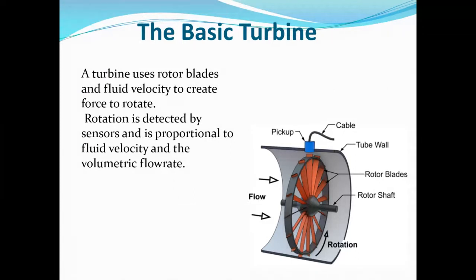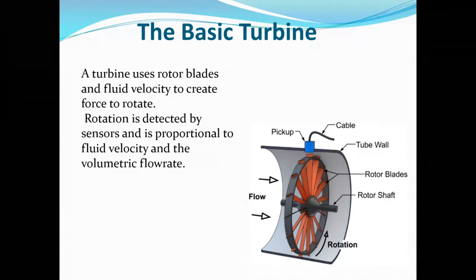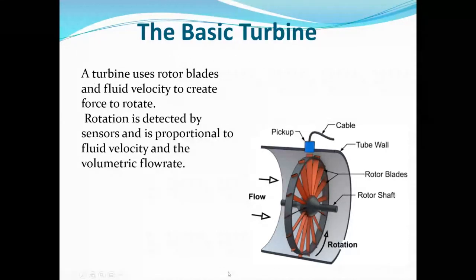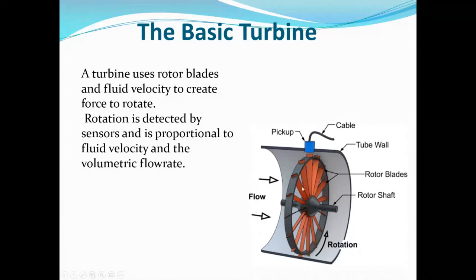Turbine meters vary in size from a relatively small half inch up to several inches and are pretty common in the oil and gas business. The basic turbine has a casing body with a turbine suspended in the flow path. As flow impinges on the pitched blades of the rotor, it causes them to turn. The blade motion is detected by a pickup which counts pulses proportional to the volumetric flow rate.